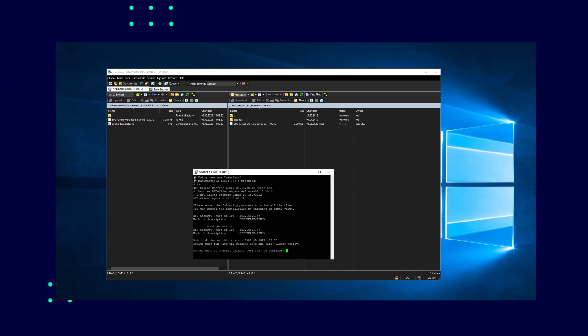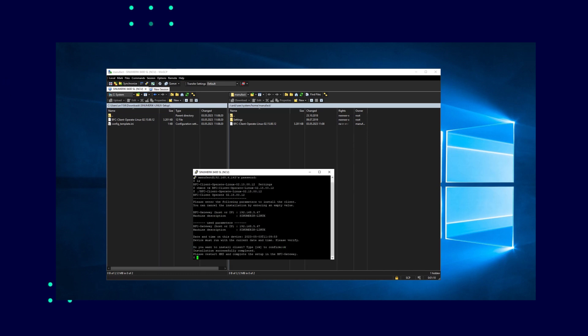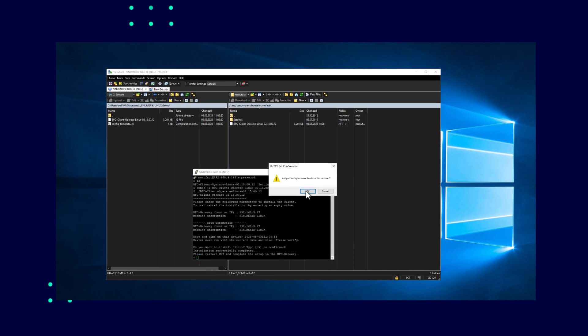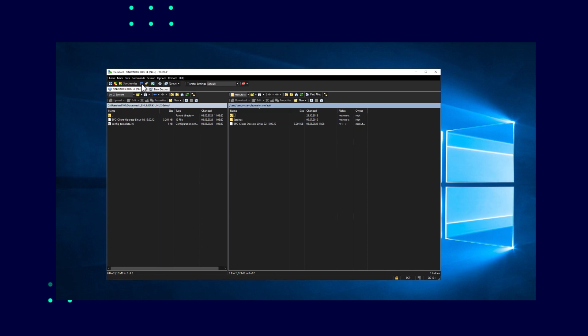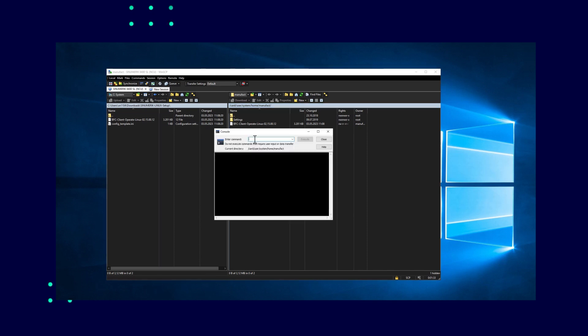The connection between the machine and the gateway will only work if the date and time of the machine match those of the gateway. If this is ensured, you can confirm with OK. After the installation, there is a note that the machine must be restarted for the BFC client to work. The machine can be rebooted either directly from the HMI of the controller or through the console, which is another function of the WinSCP.